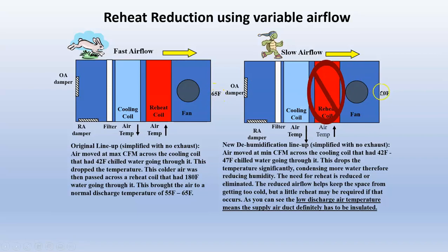This was 65, this is 50. I'm not heating it back up. Some people say, well, you're going to freeze everybody. Well, you have to be careful. It takes some time to figure it out. But by slowing the airflow down, you're going to introduce this colder air at a slower rate. The main thing to worry about when you do this is I've dropped this to 50. I better have some good duct insulation or I'm going to sweat.